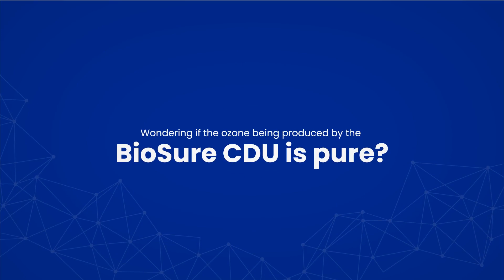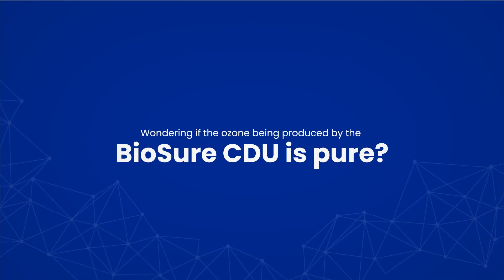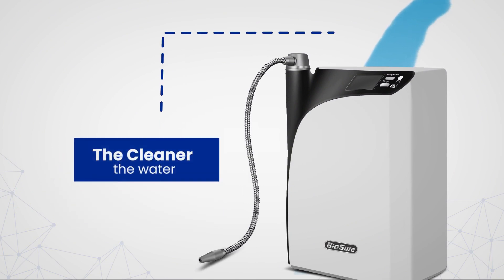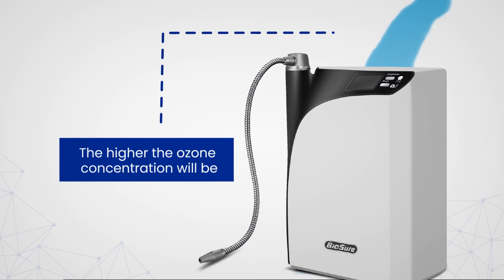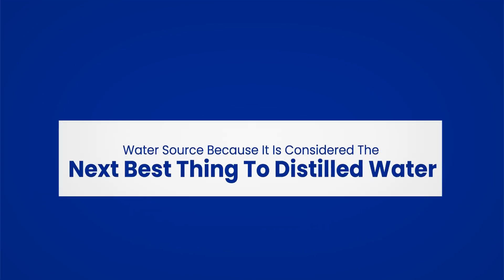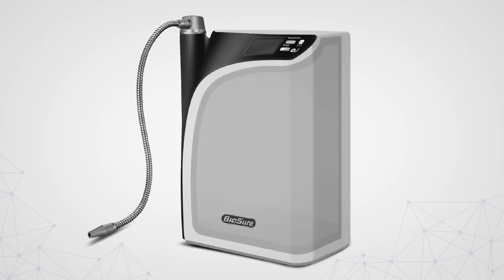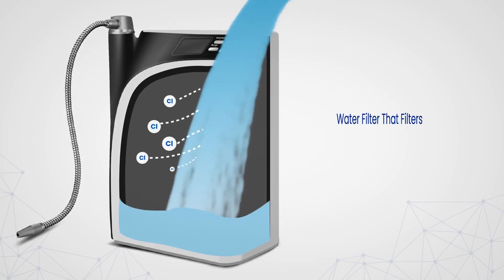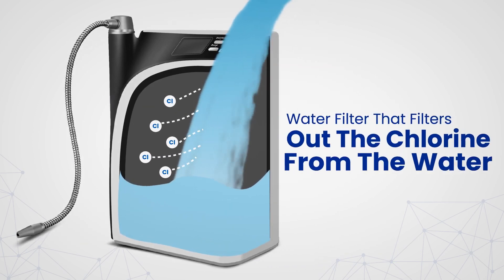Wondering if the ozone being produced by the BioSure CDU is pure? It depends on the water you're putting into the BioSure CDU. The cleaner the water, the higher the ozone concentration will be. Therefore, we recommend you to use reverse osmosis water as the water source, because it's considered the next best thing to distilled water. However, if not a reverse osmosis water system, then install a high-quality water filter that filters out the chlorine from the water.